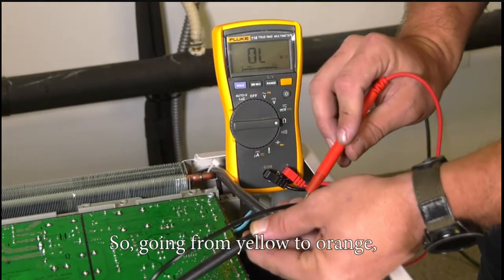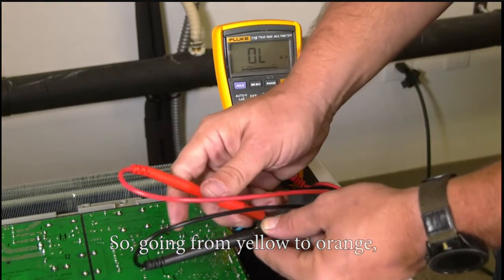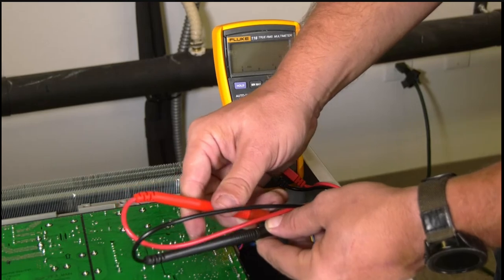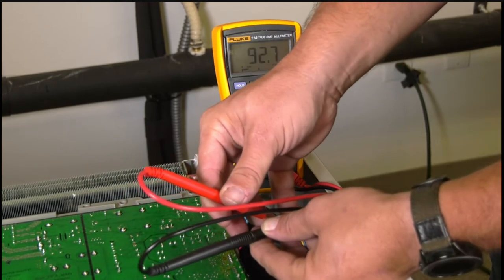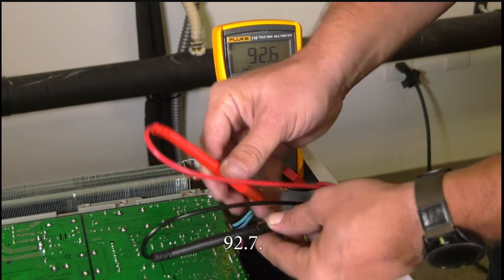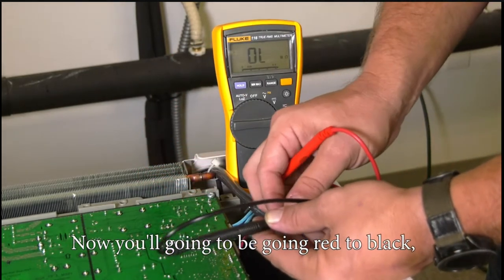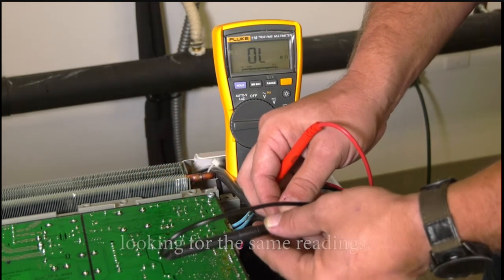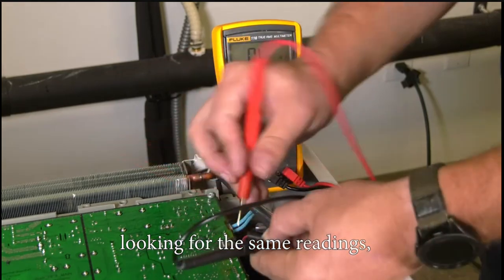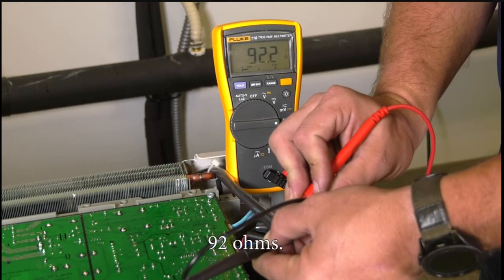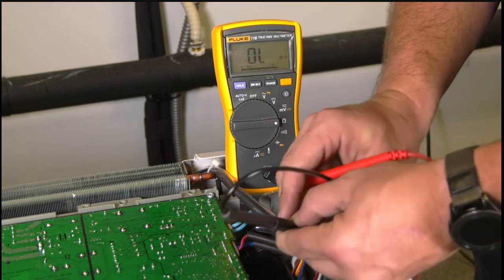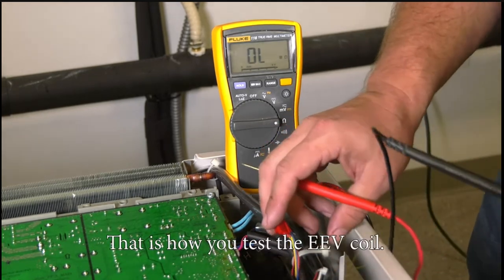Going from yellow to orange, 92.7. Now you'll be going red to black, looking for the same readings, 92 ohms. That is how you test that EEV coil.